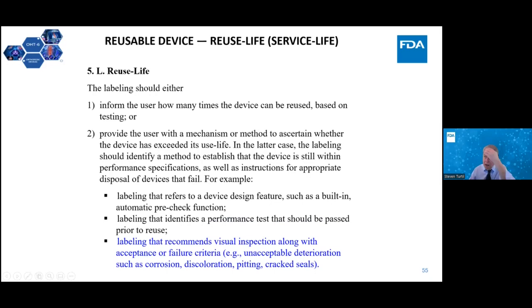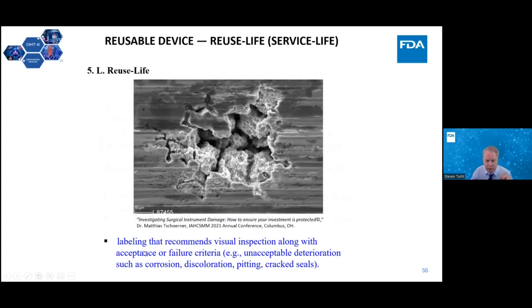So how and why is this done? I want to show you again, this is the last bullet, labeling that recommends visual inspection along with acceptance or failure criteria. The devices I work with the most are orthopedics. There are a lot of metal devices and they just wear through with time. They're corroded by the different chemicals that are used for reprocessing, maybe even the sterilant. So this is another high magnification scanning electron micrograph of that type of corrosion.